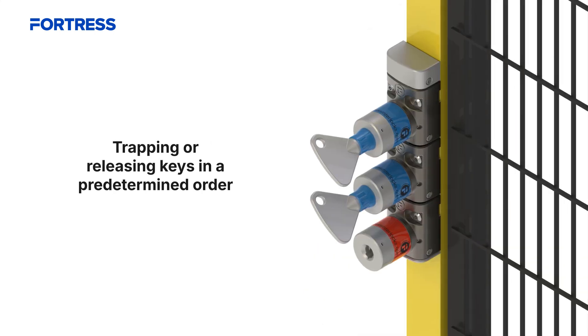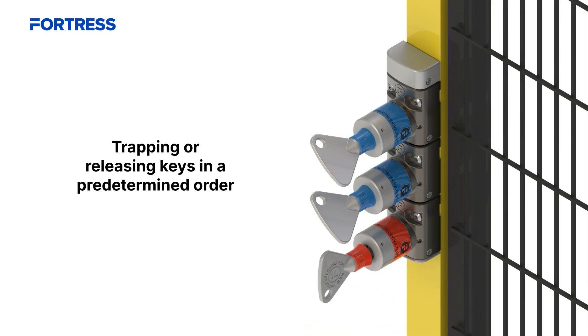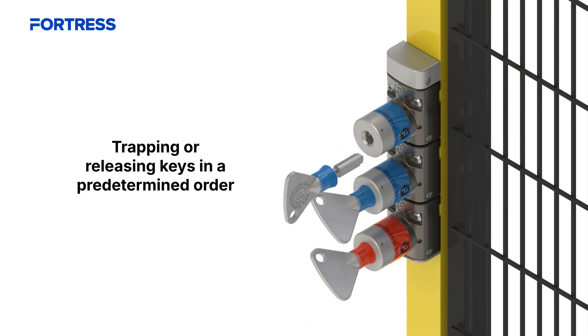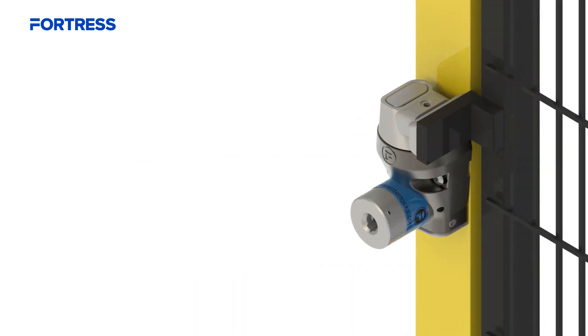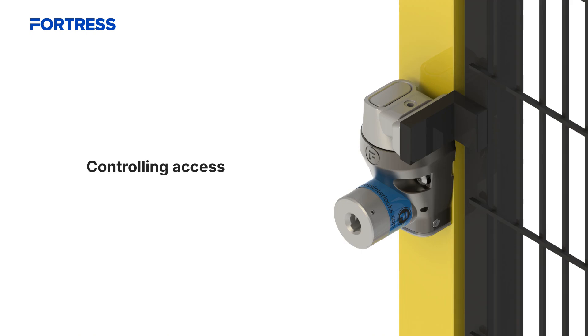Next, a key exchange device accepts one or more keys from the previous step in the sequence and releases a key or multiple keys for the next step, ensuring the correct sequence of events has been followed. To enter a safeguarded space, an access lock is used.